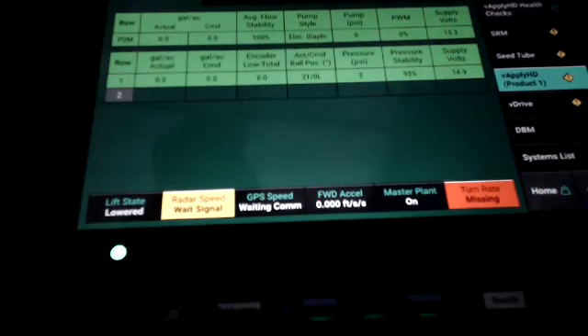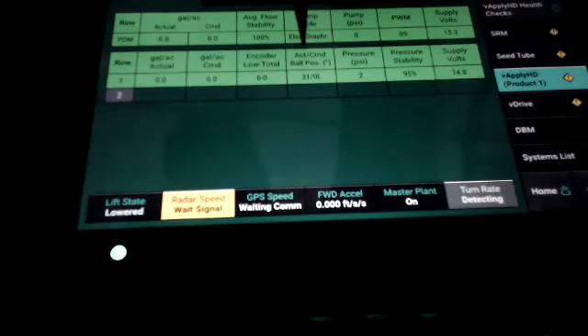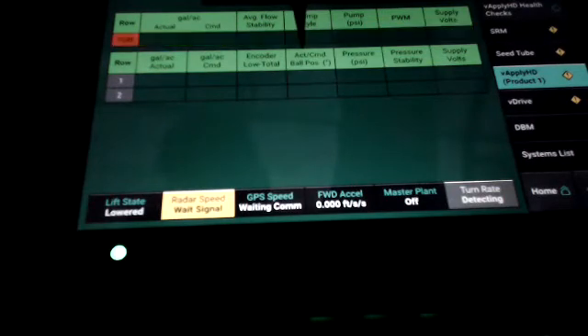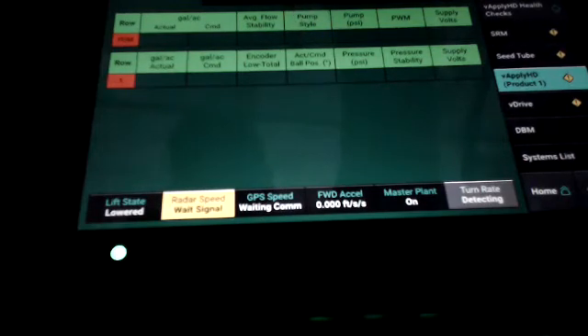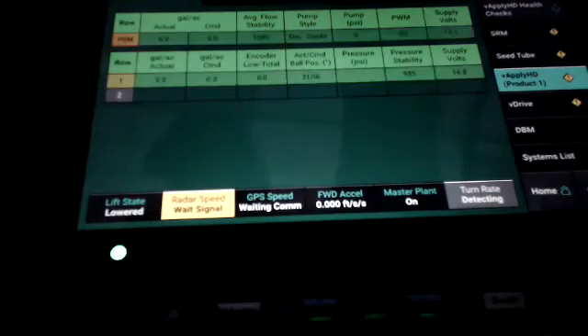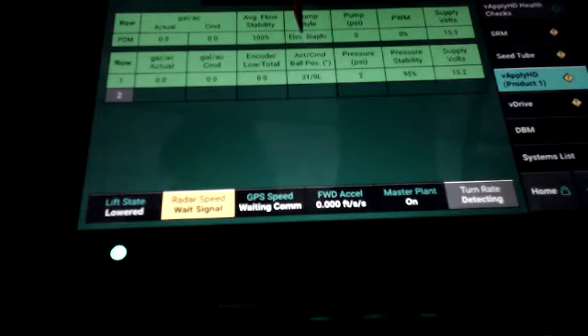So that should turn yellow. If you were to be operating like that, that would turn yellow. I don't know if it'll do it here on the test stand, but we'll maybe give it a second here and see what happens. So I hit reset modules, and we're detecting devices. And I can hear the HD trying to find its home. It doesn't look like it's going to do that for us, but you know something's either wrong with the head or the motor if these two numbers are not jiving with each other.